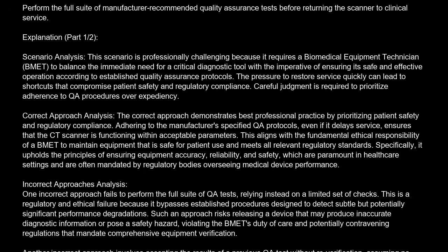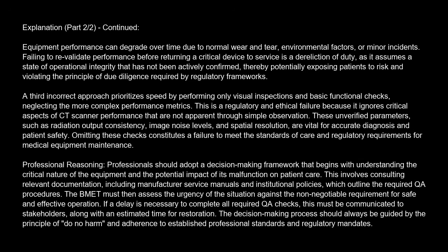Another incorrect approach involves accepting the results of a previous QA test without re-verification, assuming no issues have arisen. This is a significant ethical and regulatory lapse. Equipment performance can degrade over time due to normal wear and tear, environmental factors, or minor incidents. Failing to revalidate performance before returning a critical device to service is a dereliction of duty, as it assumes a state of operational integrity that has not been actively confirmed, thereby potentially exposing patients to risk and violating the principle of due diligence required by regulatory frameworks.